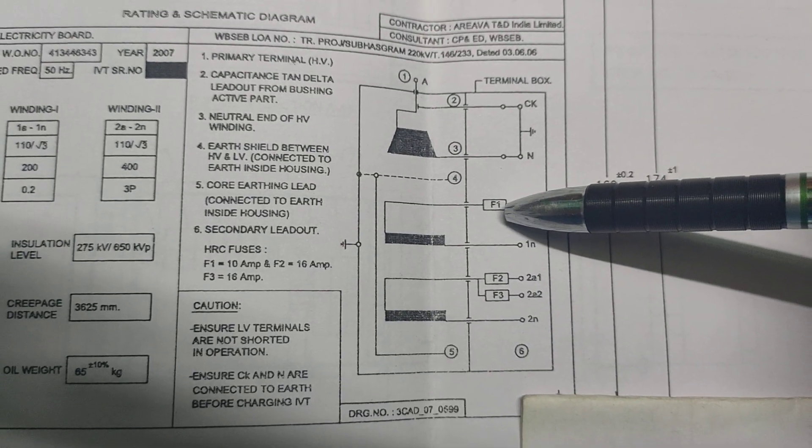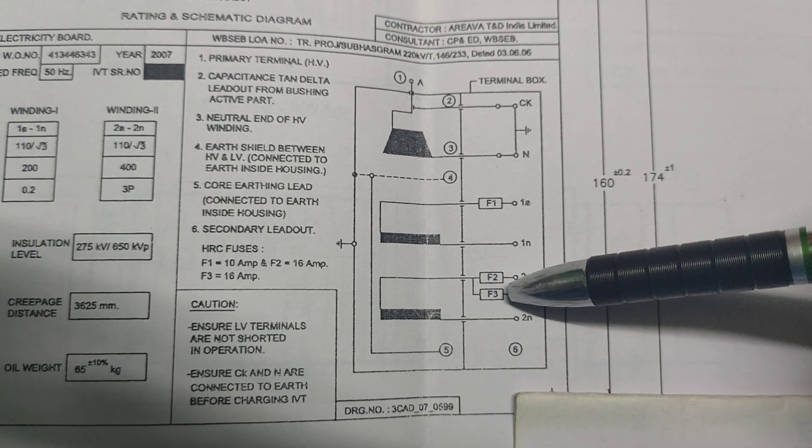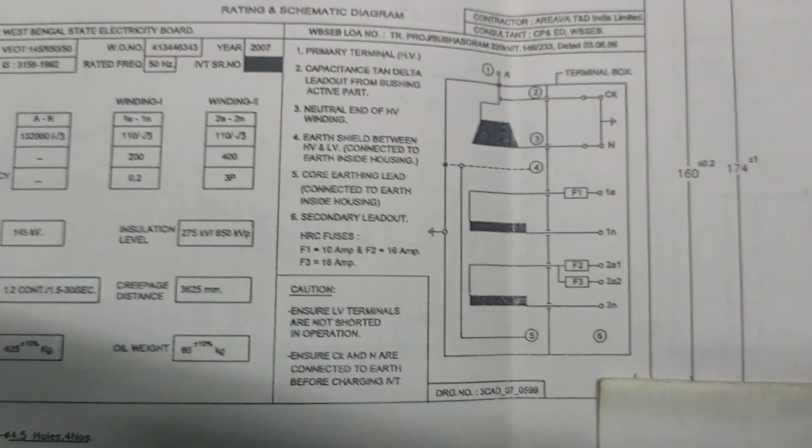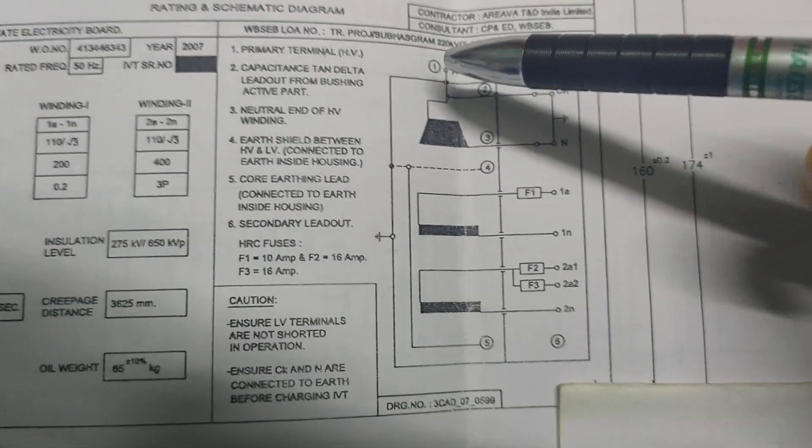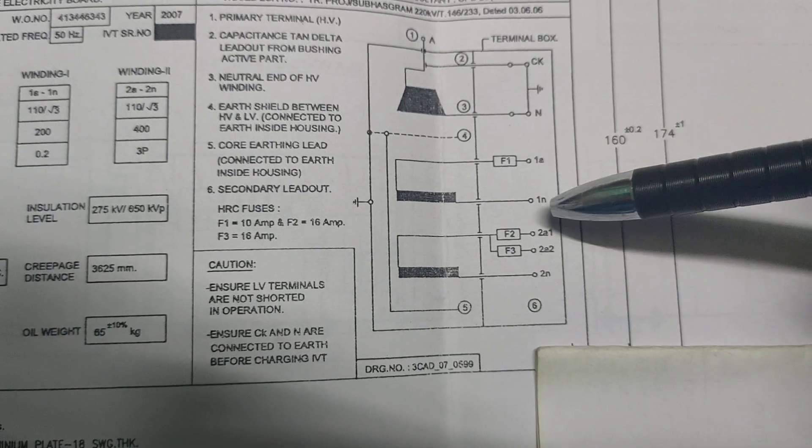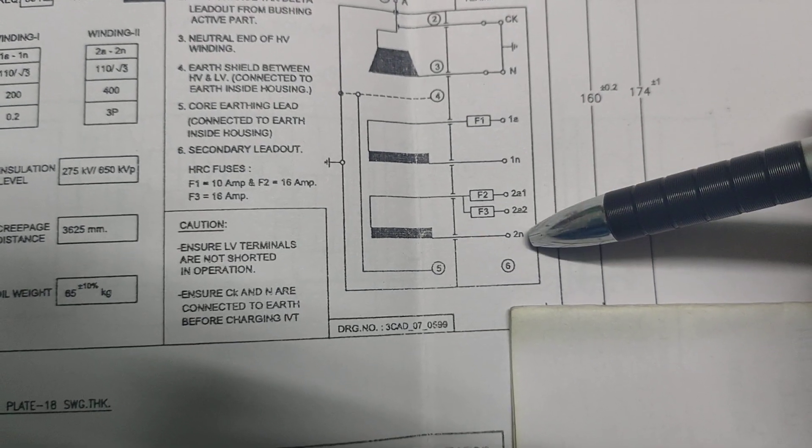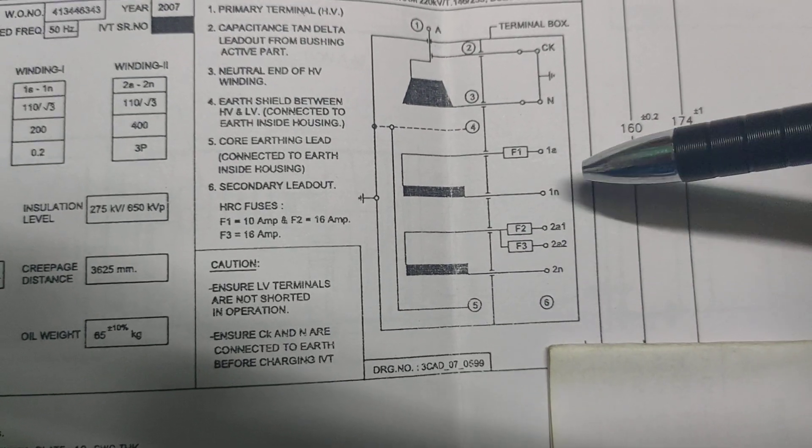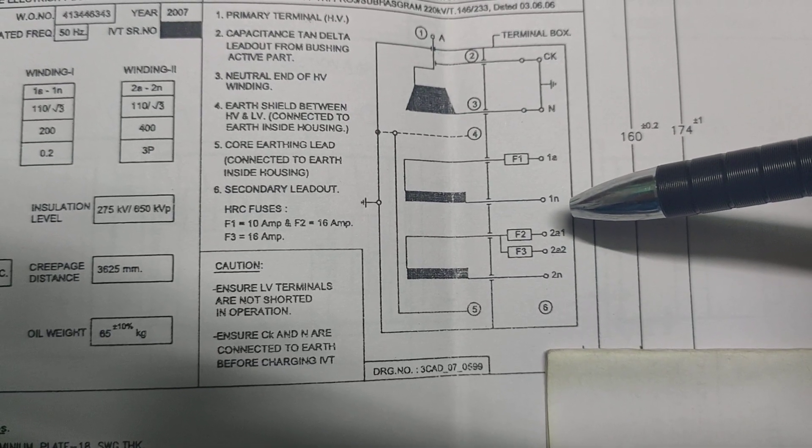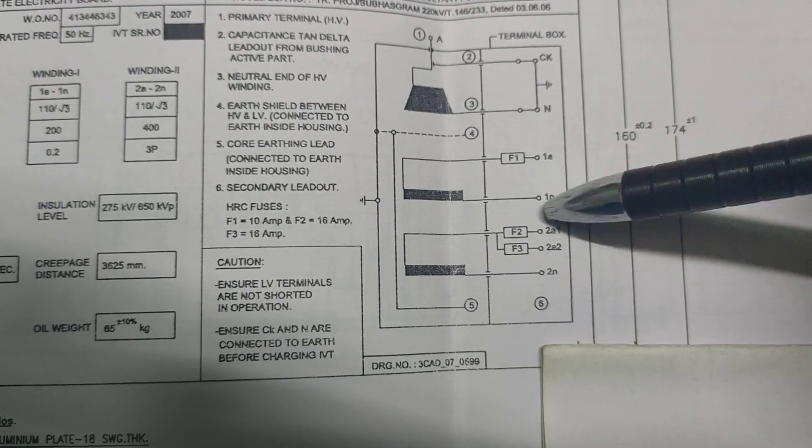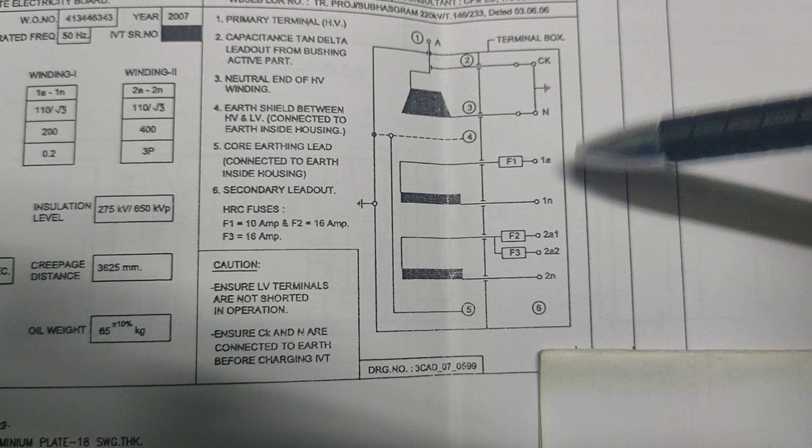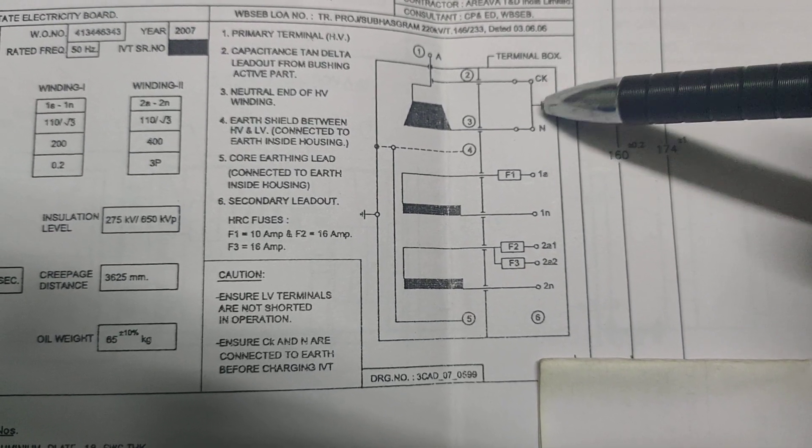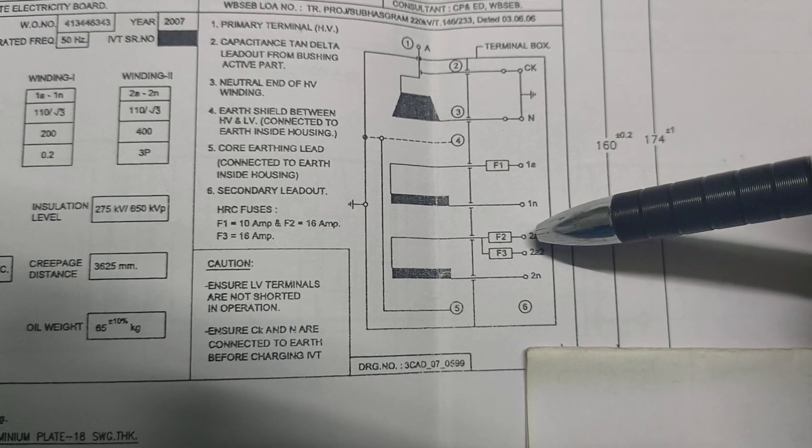6 is the secondary leadout. The HRC fuse is used in the first winding and second winding. First winding uses a 10 ampere fuse and the second winding uses 16 ampere fuses, F2 and F3. This is the pictorial representation of the inside diagram. A and N is the primary, and 1a1n and 2a2n are the secondary windings. Cautions should be followed: ensure the LV terminals are not shorted in operation, and ensure the Ck and N are connected to earth before charging.